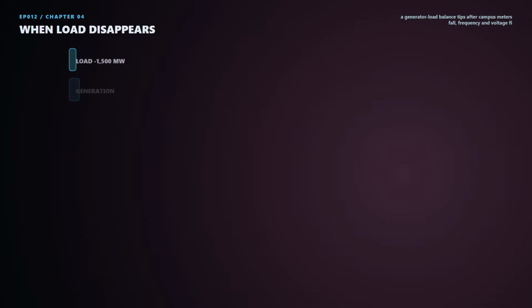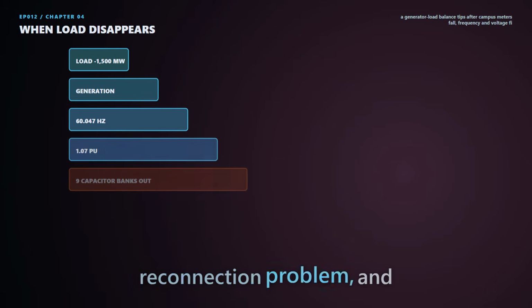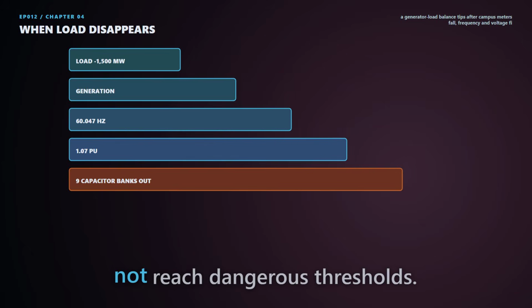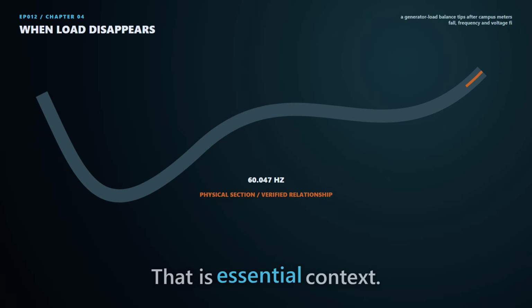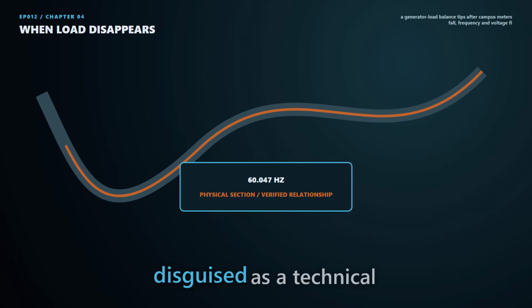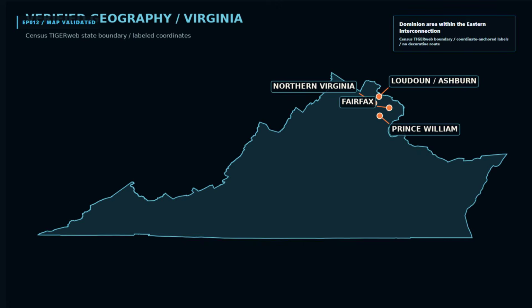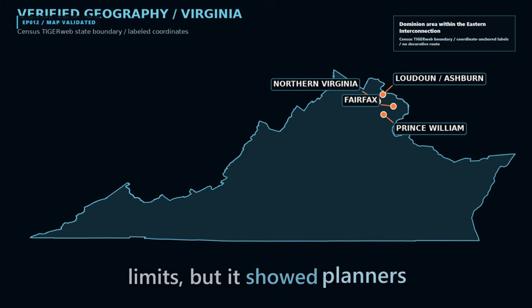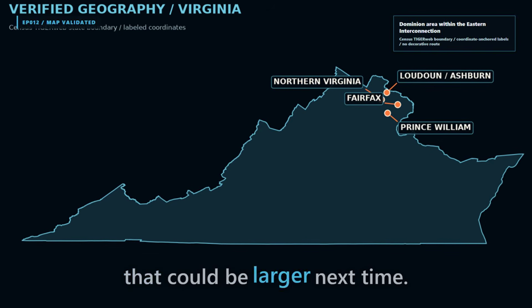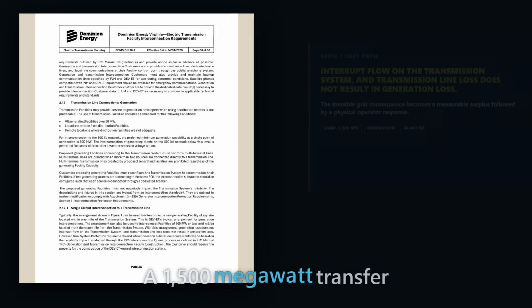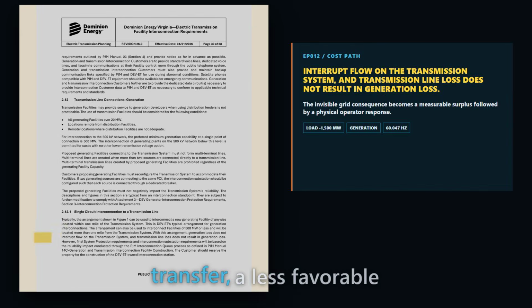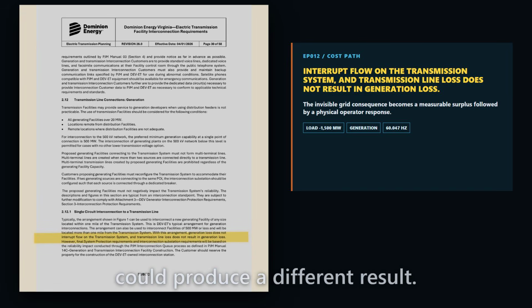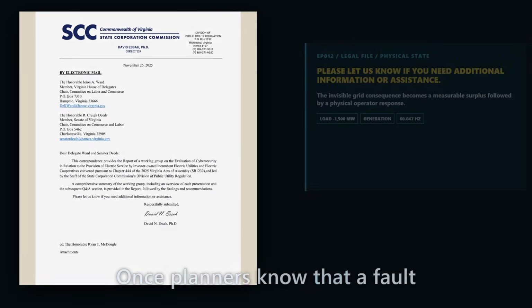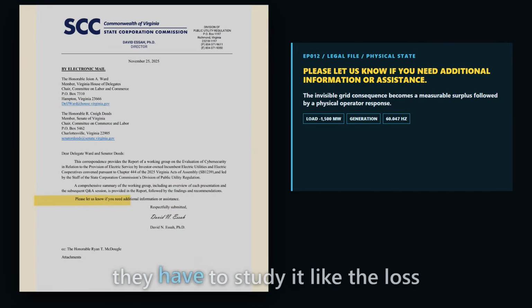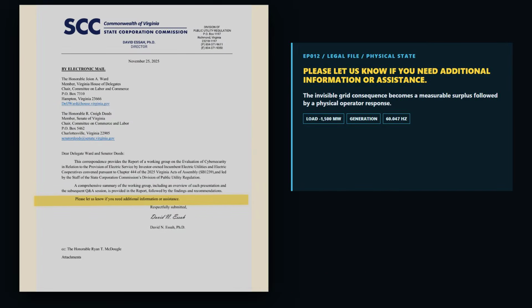NERC says the July event did not create a significant reconnection problem, and voltage and frequency did not reach dangerous thresholds. That is essential context. This was not a near collapse disguised as a technical memo. The event stayed within reliability limits, but it showed planners a load loss mechanism that could be larger next time. A 1,500 megawatt transfer was manageable. A larger transfer, a less favorable generation pattern, or a badly coordinated return could produce a different result. Once planners know that a fault can remove this much demand, they have to study it like the loss of a power plant, only in reverse.